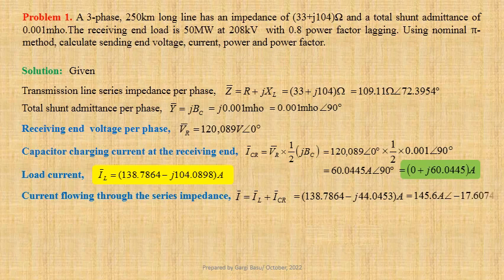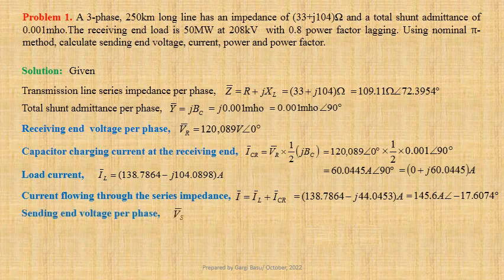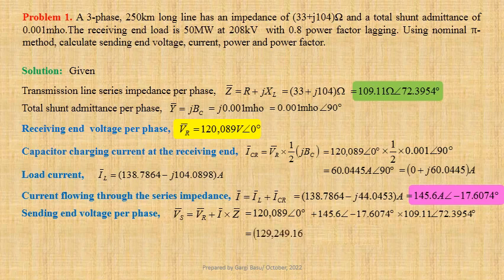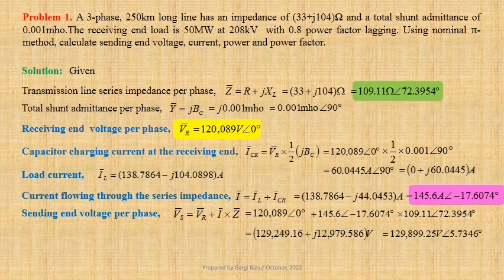Now we shall compute sending-end voltage per phase. VS equals Vr + I × Z. Using values we get 120,089 ∠ 0° plus 145.6 ∠ −17.6074° × 109.11 ∠ 72.3954°. That gives us 129,249.16 + j12,979.586 volts, which may be written in polar form as 129,899.25 volts ∠ 5.7346°.